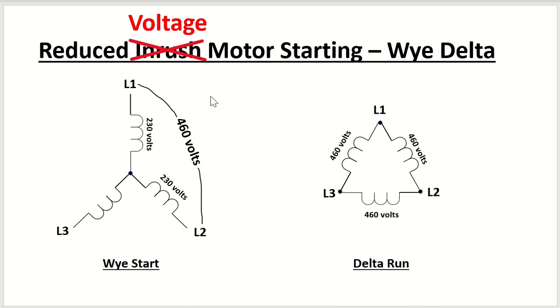You may hear the term reduced voltage, and you'll see here why it's sometimes termed reduced voltage motor starting. When you start the motor in the Y configuration and you have 460 volts in this example from L1 to L2, and you would also have 460 from L1 to L3, L2 to L3, you only put 230 volts or half the voltage across each inductor winding inside the motor. You start the motor in that configuration, which is reduced voltage on the winding, and then you switch it to the delta configuration here, where you have full voltage on each winding, 460 volts.